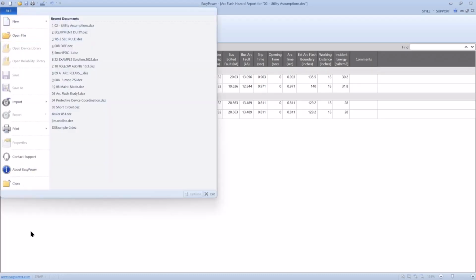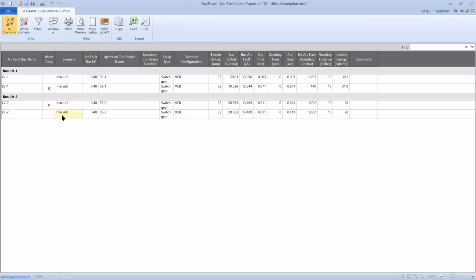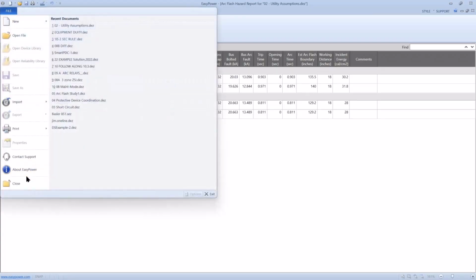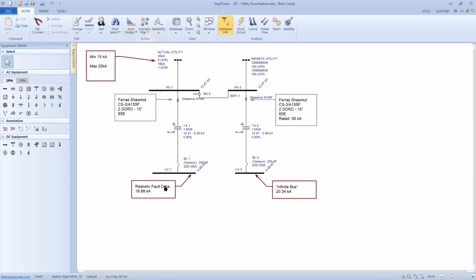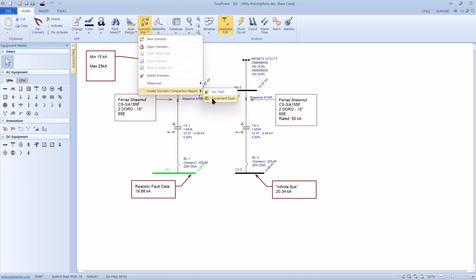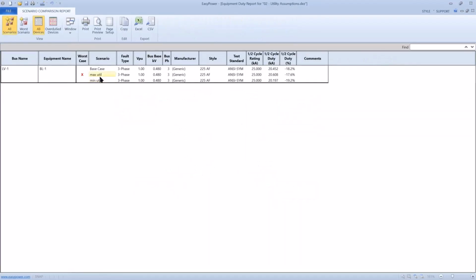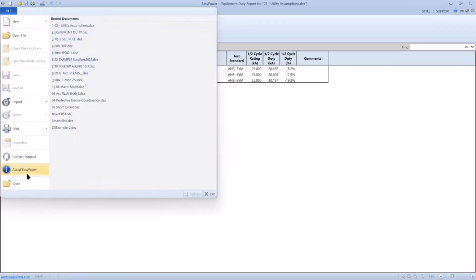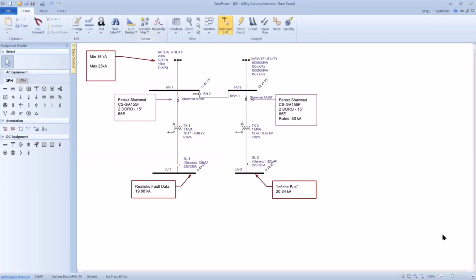Okay, so now I can do the same thing. Now, you might say, well, why get maximum data, the infinite source? And the answer to that is for equipment duty purposes. So if we go back and do that same report for equipment duty, let's just pick out this one, and do a scenario manager, create scenario report for equipment duty. We see the worst case then for equipment duty is the max value. So it has its purpose, and it's a good rule of thumb as a backstop for equipment duty calculations.